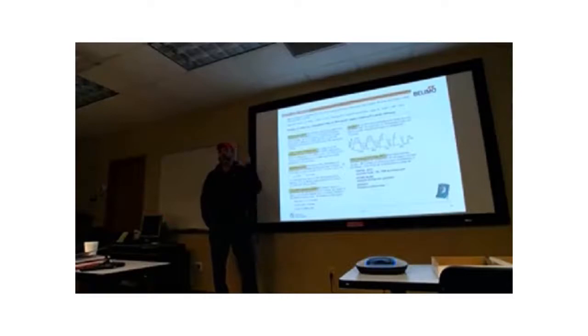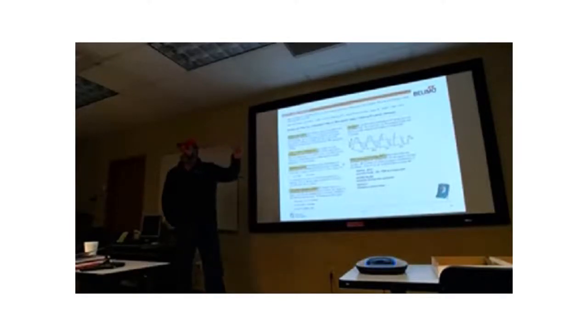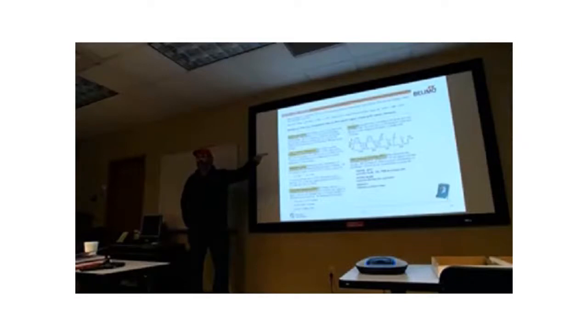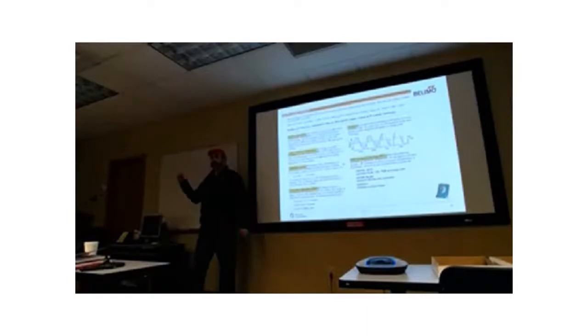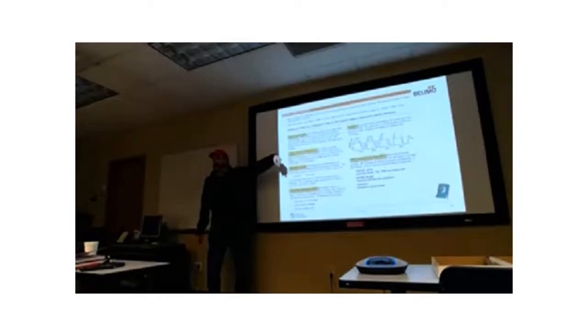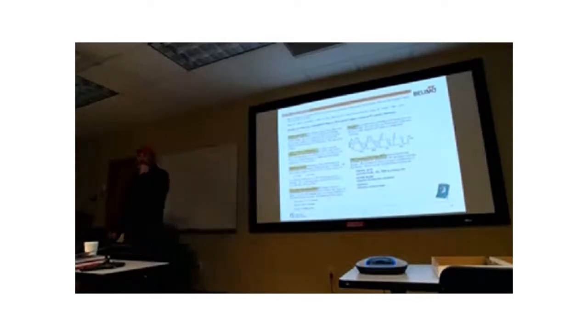What you do is you close one digital output, apply 24 volts, say, and the actuator drives in one direction. If you close the other digital output, it drives in the other direction. If both digital outputs are open, then it doesn't do anything, it stays where it is. That's why we call it tri-state, because it's either driving one way, driving the other way, or it's at null. One of those three states is what the actuator is in at all times. It's used for VAV boxes. If you work on VAV boxes, you've seen this signal. It's typically a floating point control.